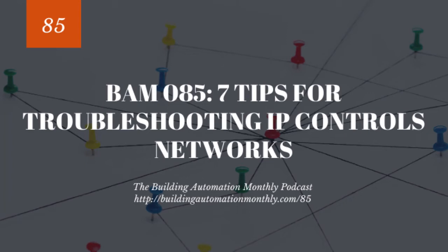So you really have to understand that, because one of the biggest issues with IP networks is IP address conflict, and that could cause some huge problems for you, especially if your IP addresses are intermingling with other systems that maybe aren't BAS controls. That's why I really recommend segmenting, at least on a subnet, your BAS network and not mixing it with a production network. So that's a whole other thing that you need to think about right there.